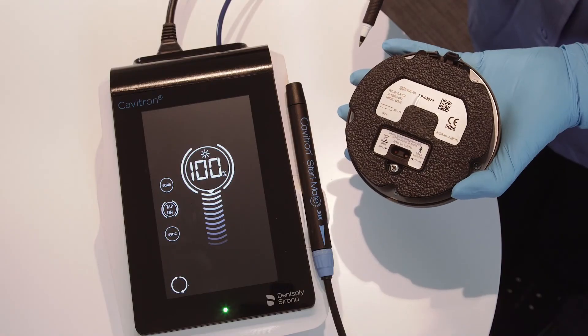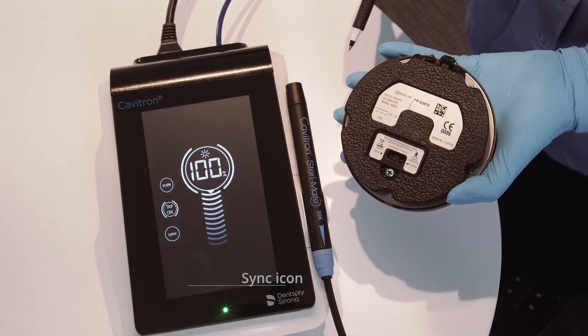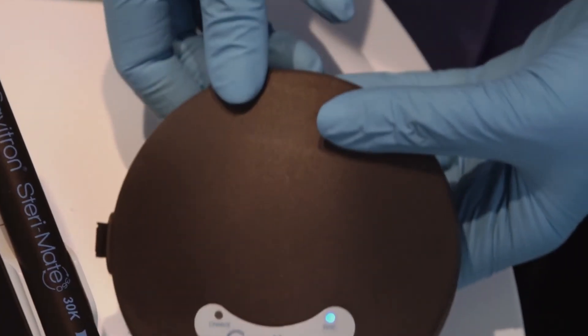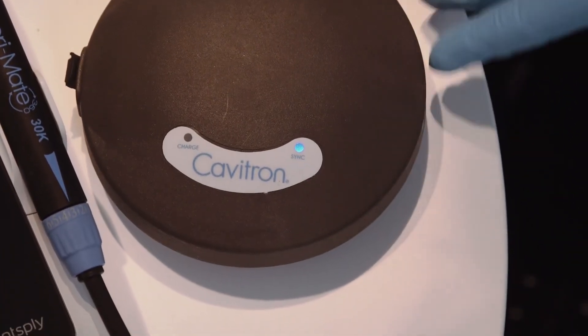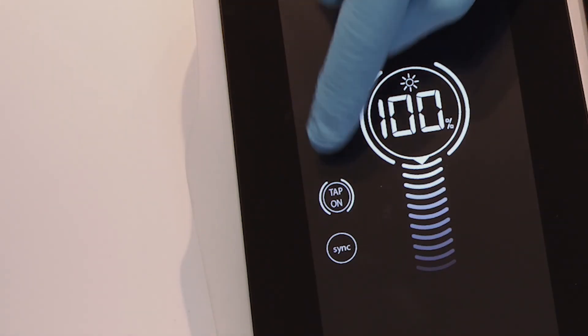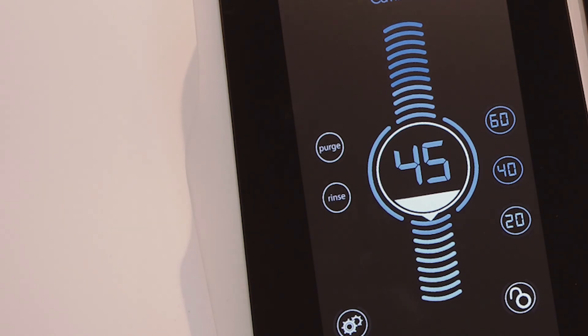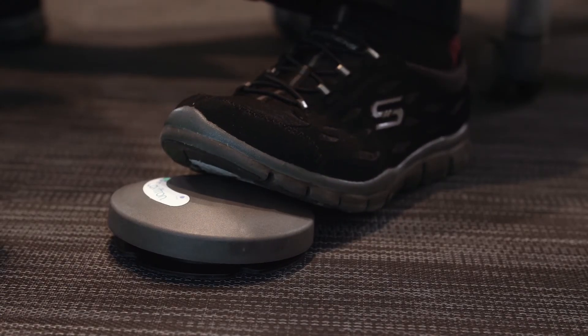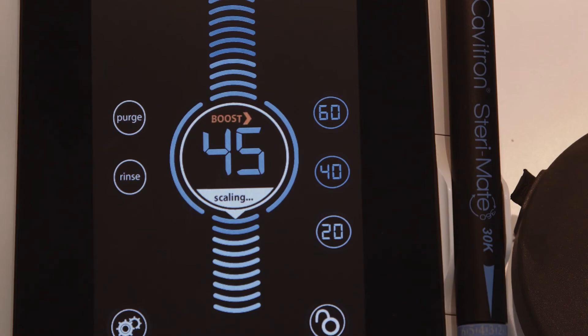Synchronizing is complete once the sync icon has stopped rotating and sound indication occurs. In order to verify that there is proper communication, tap the scale icon to return to the main screen. Depress the foot pedal to the second position and ensure that boost is activated.